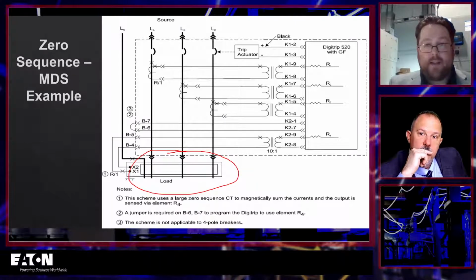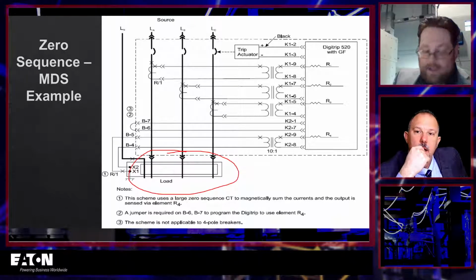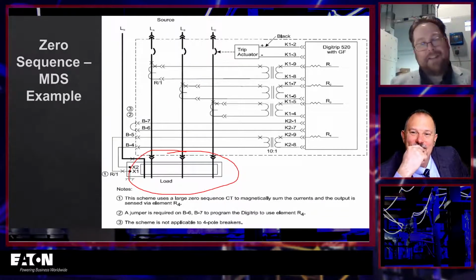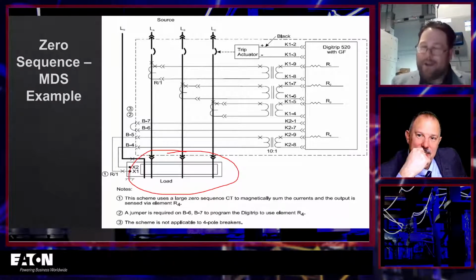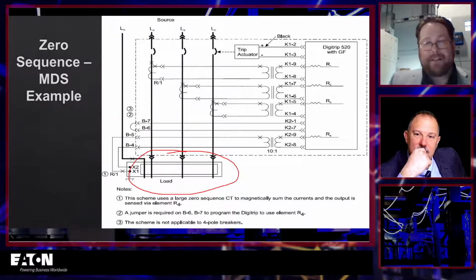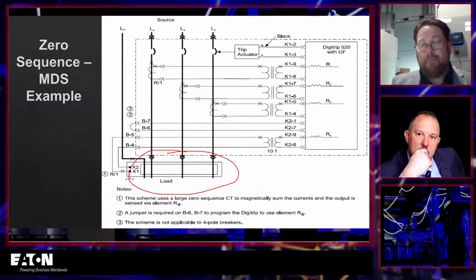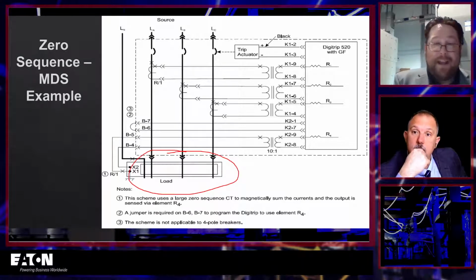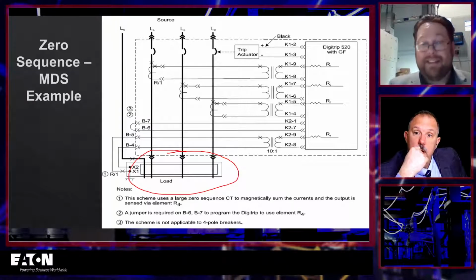And he does this and he realizes there's a motor behind him that's running. And he's looking at the drawings, and this motor's running, but this motor's fed from the side of the switchgear he just turned off. And he's looking at this, kind of like, okay, what's going on here? Maybe someone wired it to the wrong side of the switchgear, right? And he starts diving into this and finds out that the manufacturer had actually bussed around the tie breaker in the back of the switchgear, had actually built the bus and bypassed the tie breaker completely.